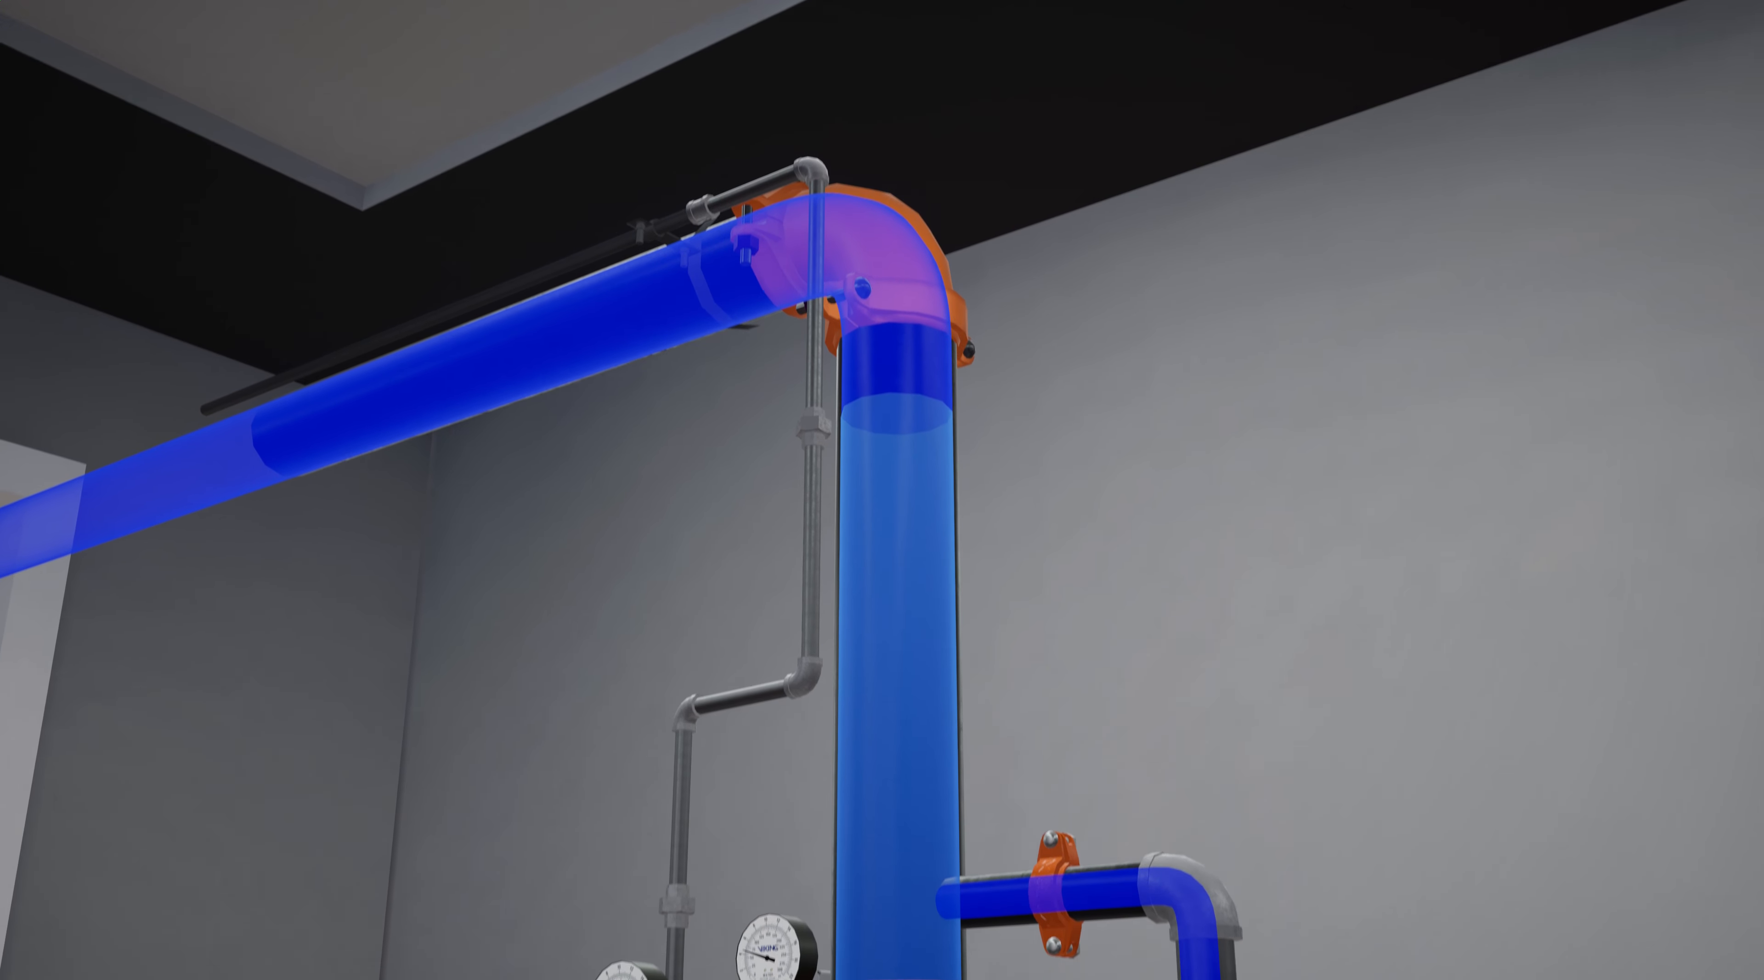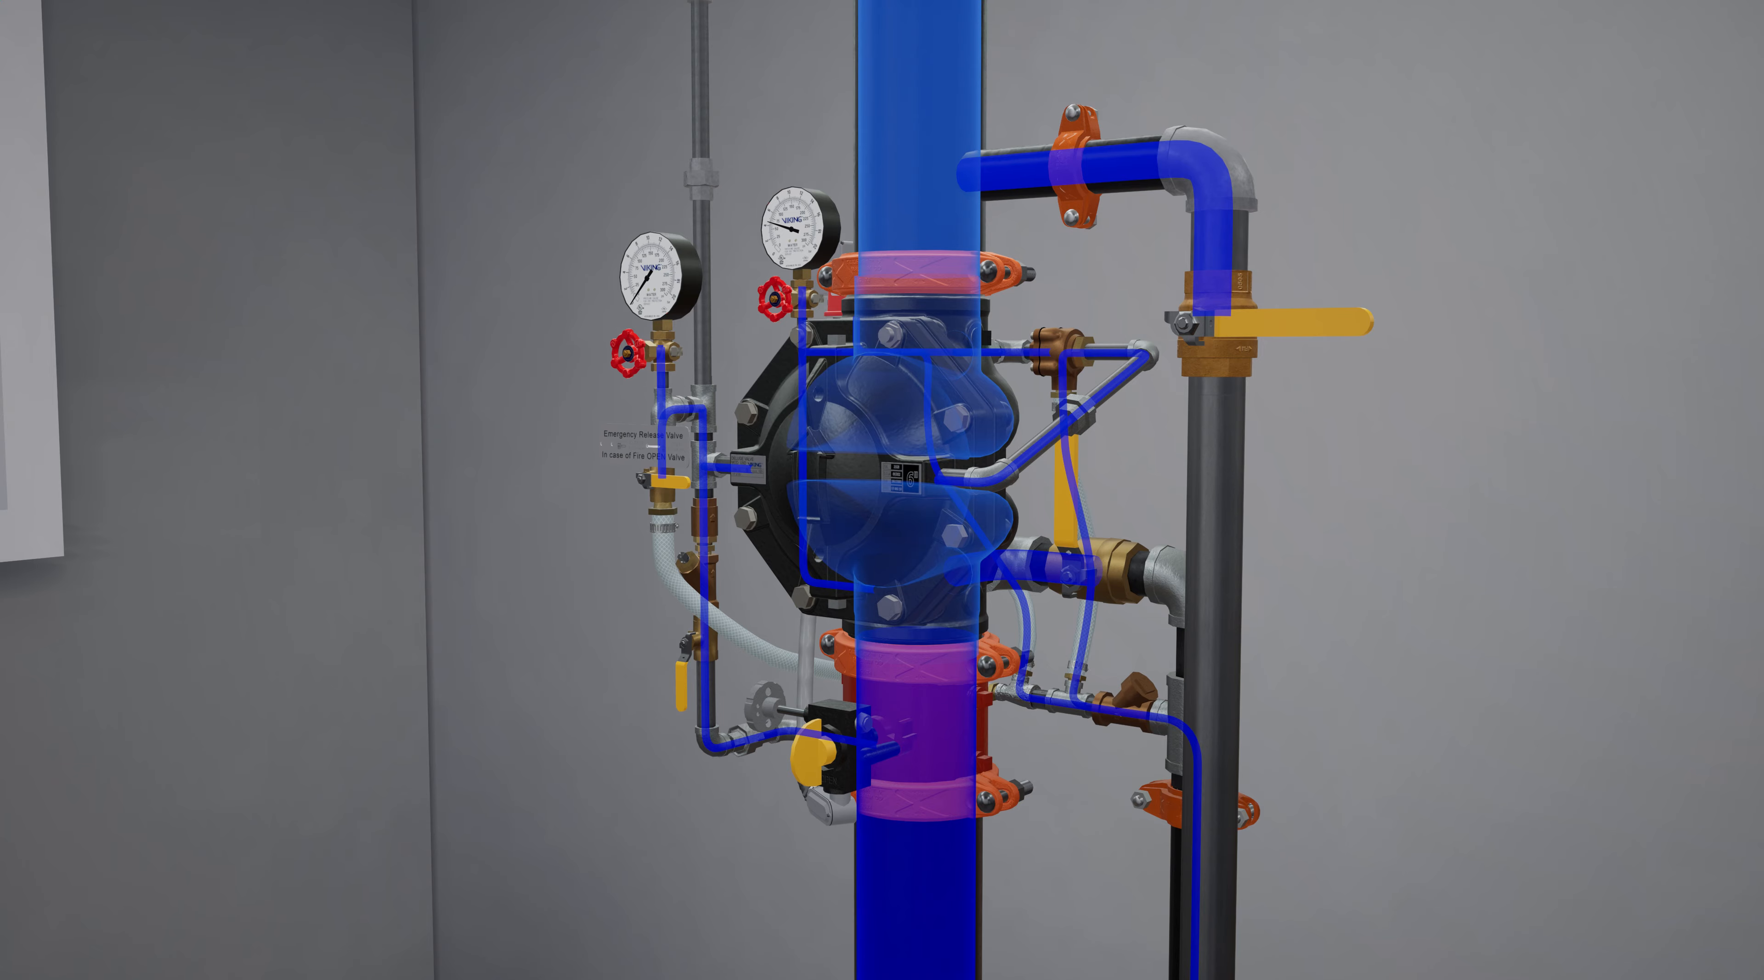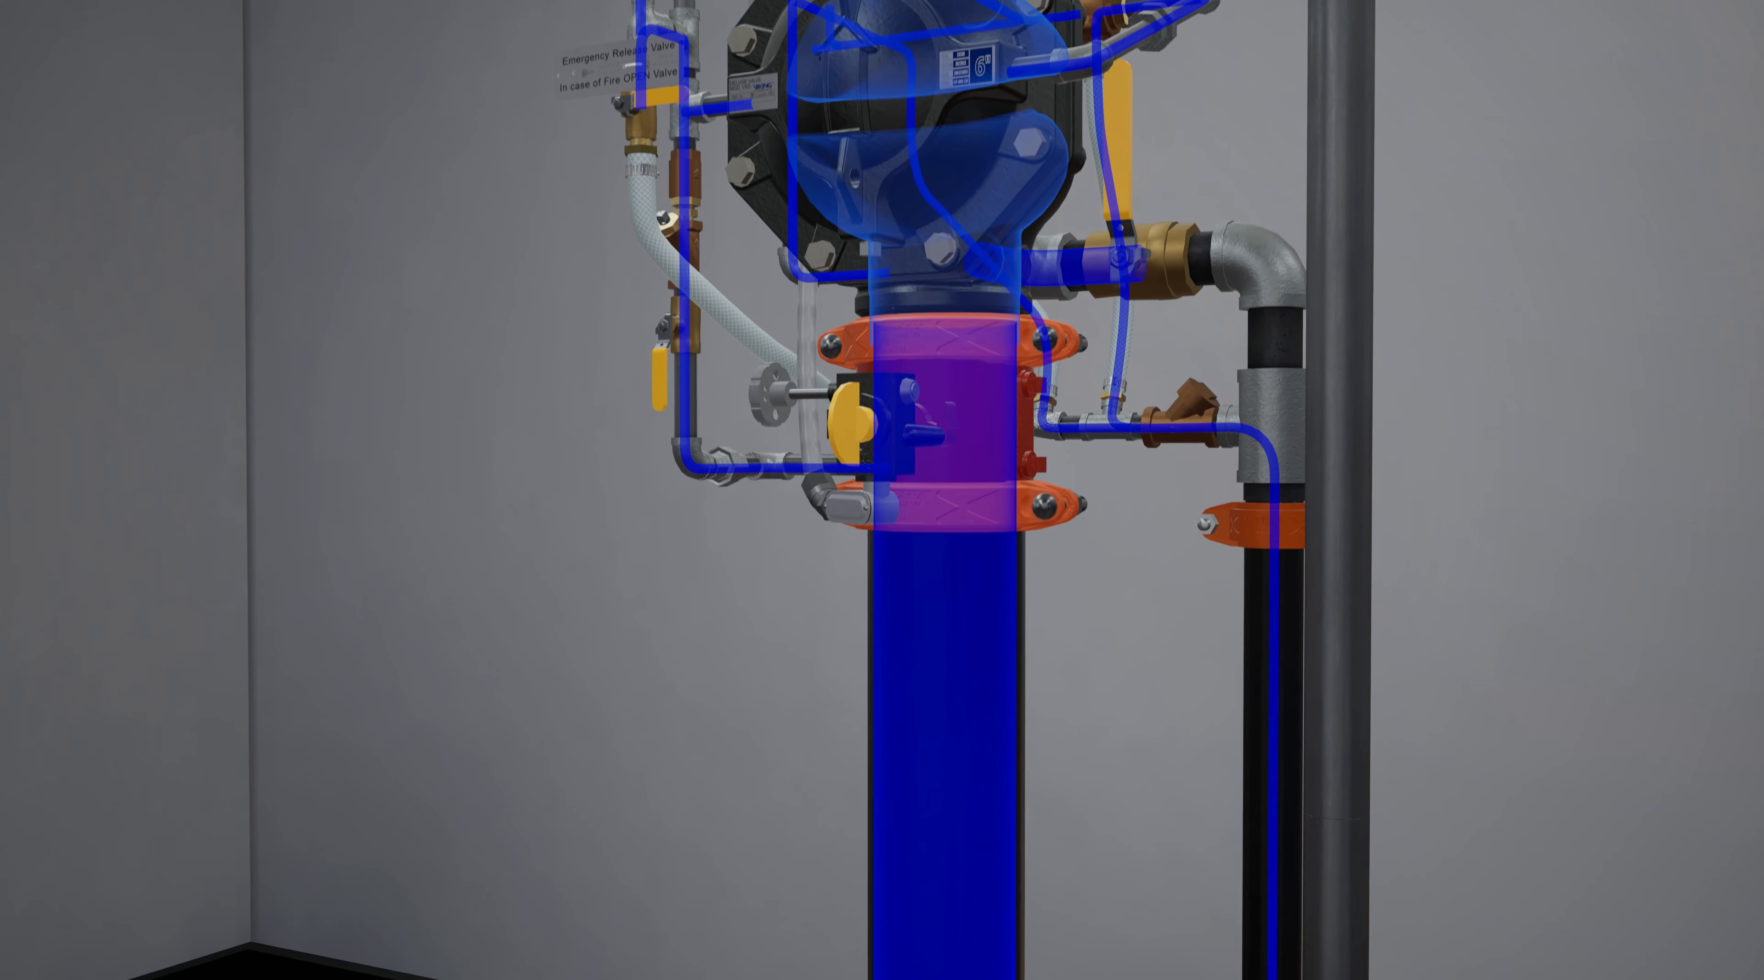Let's go through the steps of resetting a hydraulic deluge system equipped with a BXV deluge valve. Let's start by closing the water supply control valve.